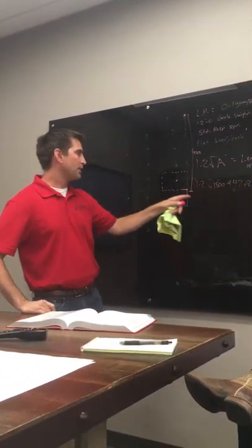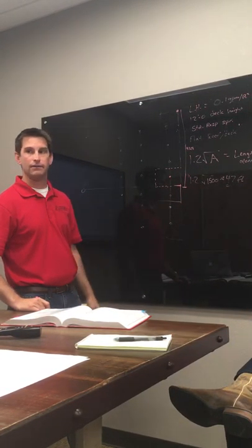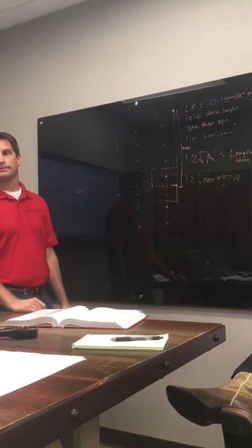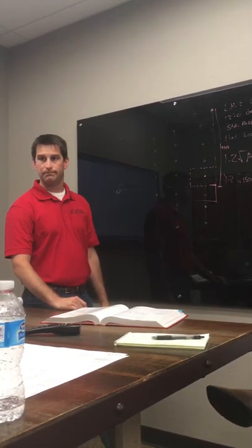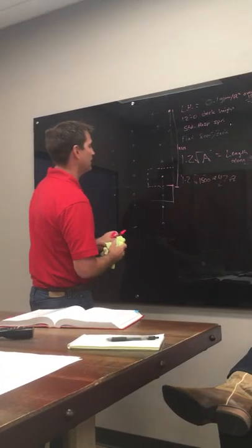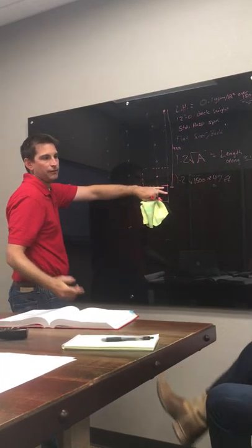So you're usually going to be more than the 47 just because of where that head falls. But you don't want to go any more heads than you actually have to. That's just bad. So if you're in the coverage area of another head, you have to include that last head as well. Correct. Yep, exactly. If your branch line is not 47 feet, if this stopped and the main was here and your branch line was just that length, you pick up the whole branch line. You can't go anywhere. So you pick up the whole thing and go to the next one.